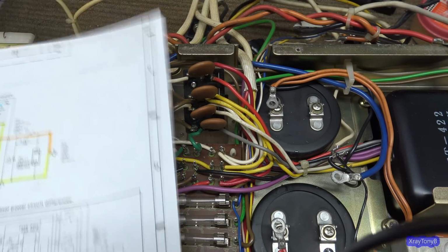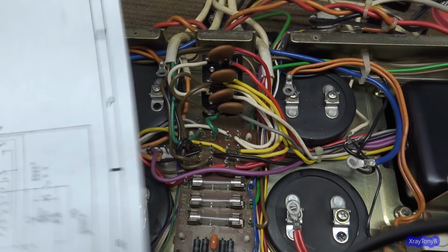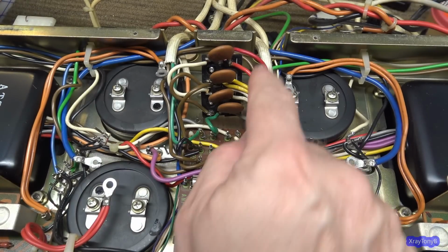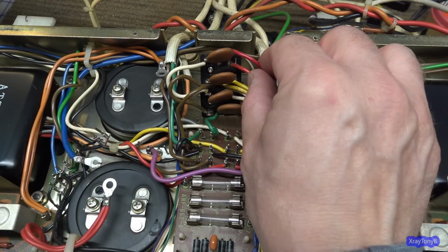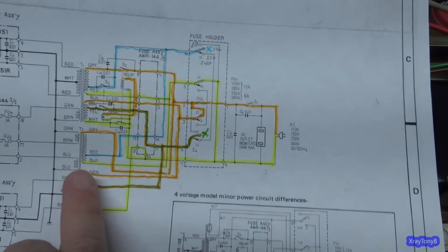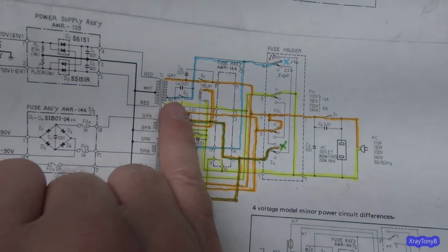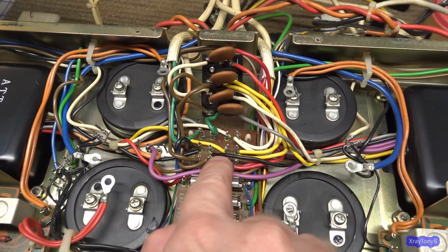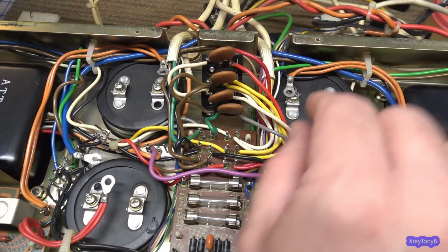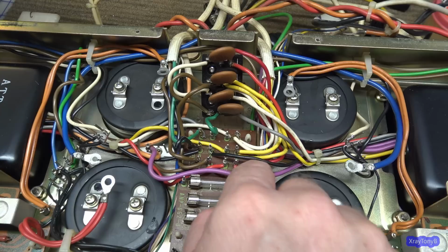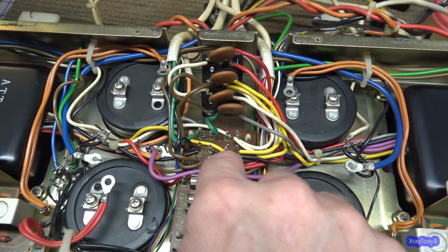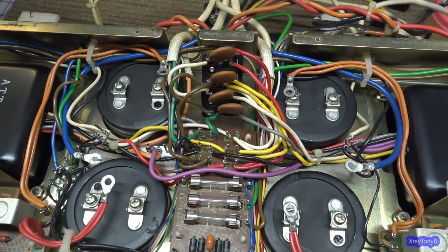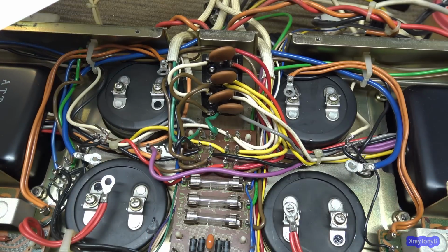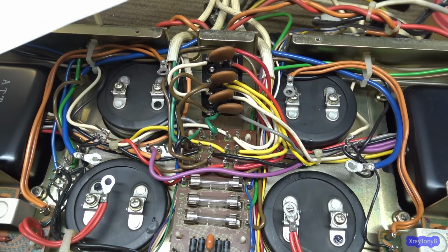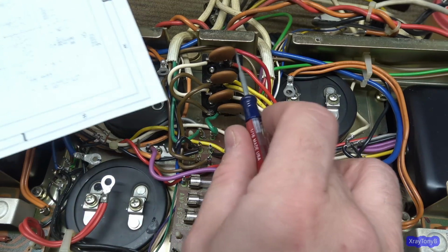Okay, here's how we're going to do this. First, I'm going to take this red wire off of this relay. You can see the red wires are right here - these are the 110 volt taps. They're tied together between here and here, you can see it. So what I need to do is, there's a jumper - see, there's two on this. These two posts are tied common, and these two posts are tied common to one another, the red posts and the yellow posts. So I'm going to remove both of these red wires off of this relay.